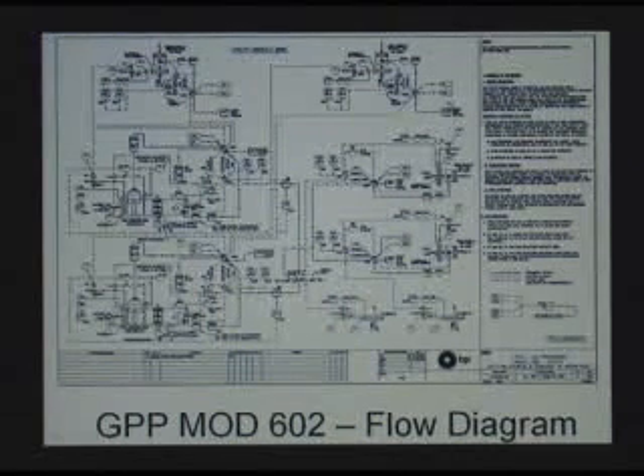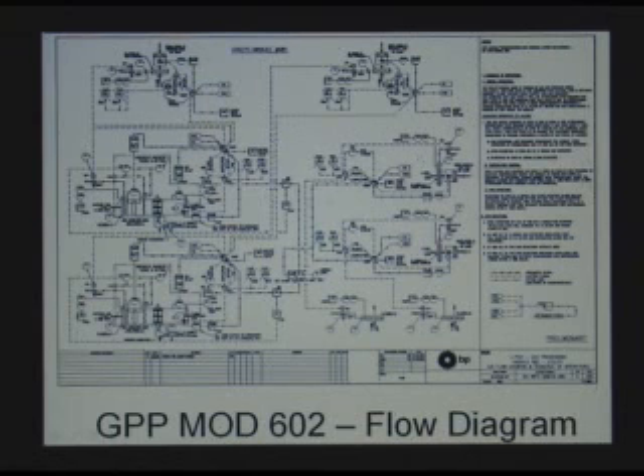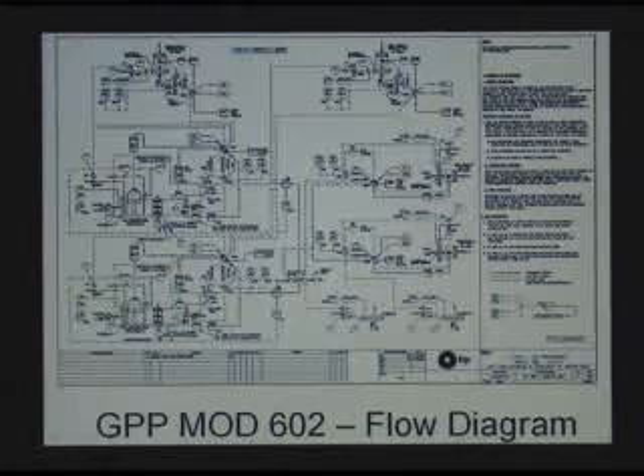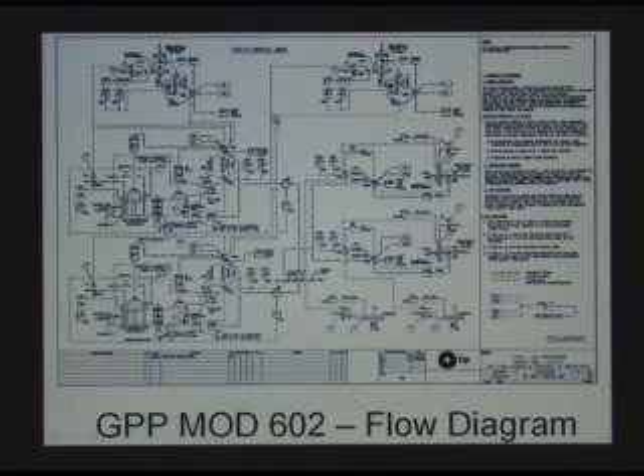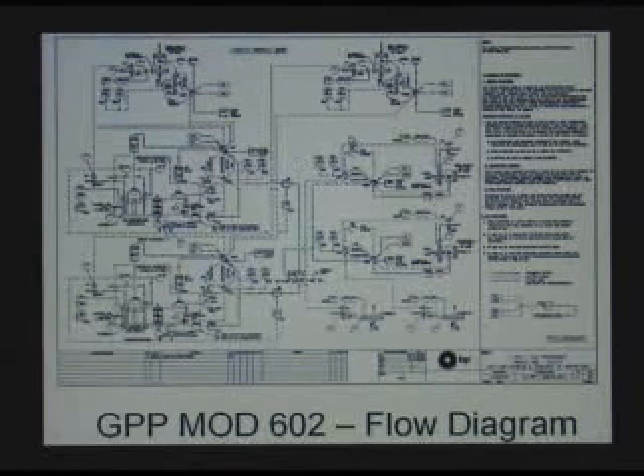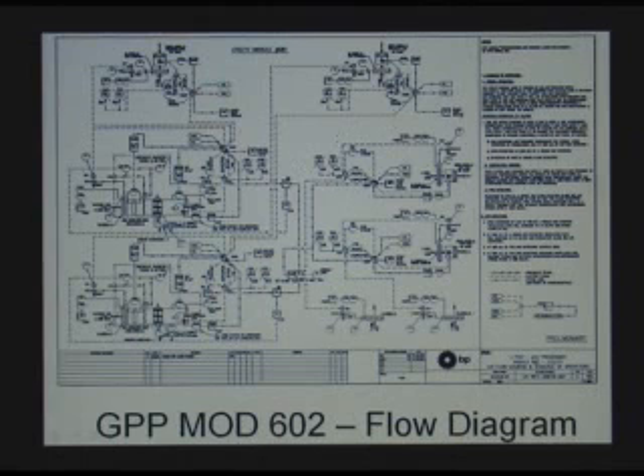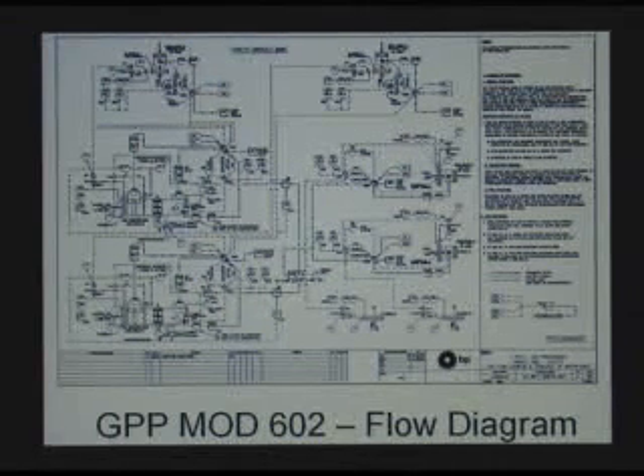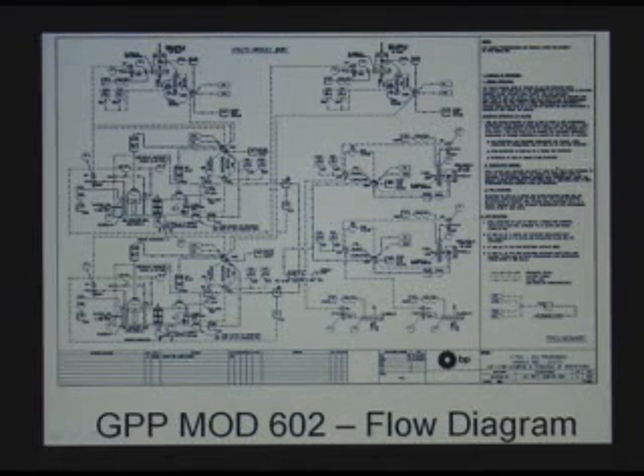This is another flow diagram that we have produced. It talks about all the controls, how we interlock every air handling unit with your exhaust fan, how it's managed, and how the temperature is controlled. And of course, those are interlocked with your fire suppression system, because in these 600 modules we do have an FE13 system. That's part of the fire suppression, which I'll go over. So that's another flow diagram.